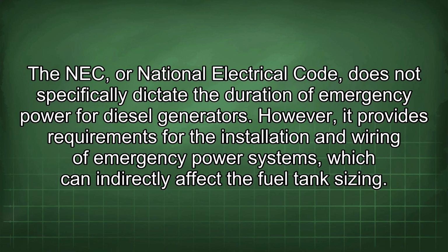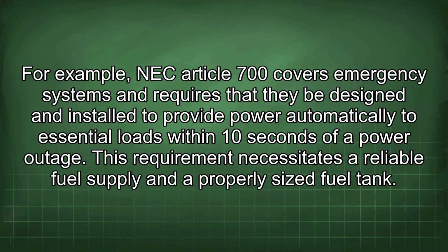The NEC, or National Electrical Code, does not specifically dictate the duration of emergency power for diesel generators. However, it provides requirements for the installation and wiring of emergency power systems, which can indirectly affect the fuel tank sizing. For example, NEC Article 700 covers emergency systems and requires that they be designed and installed to provide power automatically to essential loads within 10 seconds of a power outage. This requirement necessitates a reliable fuel supply and a properly sized fuel tank.